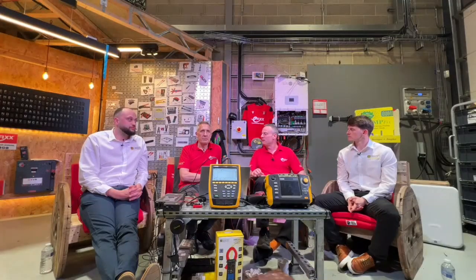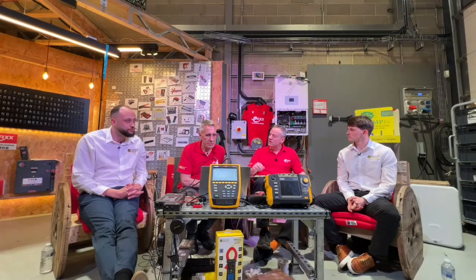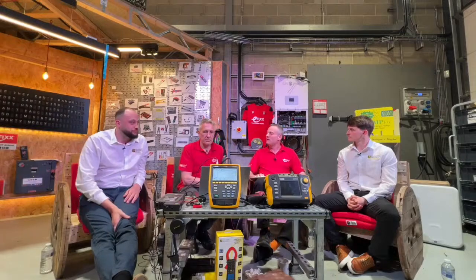If you installed a cable over a period of time for maybe a factory unit, and then they start adding more and more kit, you don't want to get a problem - maybe those overcurrent protection devices aren't as accurate as some in the future. You could start saying, hang on, we've got a potential problem here if the cable's at its maximum from that design. You could check if the cable is capable of taking that current. You'd like to think an older installation is one you'd have to take a closer look at - you'd hope a new one would be designed correctly, but of course it depends.